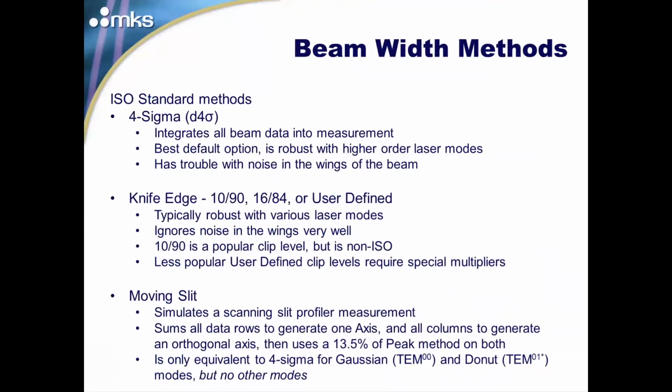There are definitely less popular user-defined clip levels that you can enter. It's important to note that with each knife edge clip level, you have to have a special modifier, a multiplier, that has to be input into the software. Otherwise, your results will not be accurate.